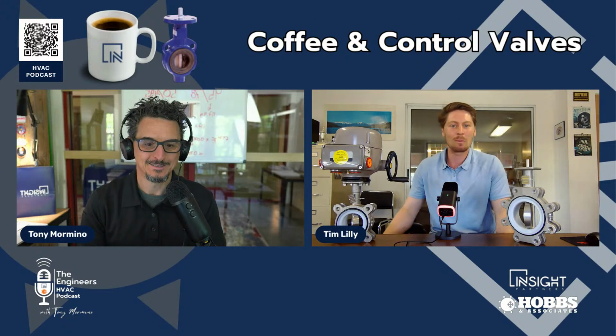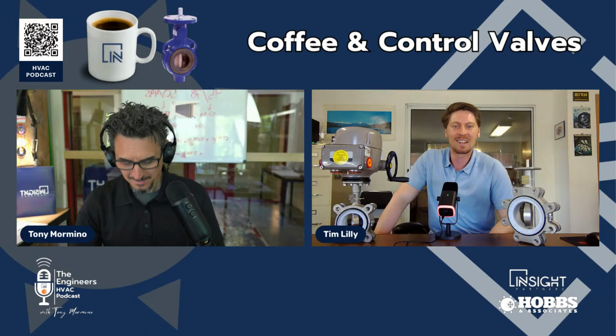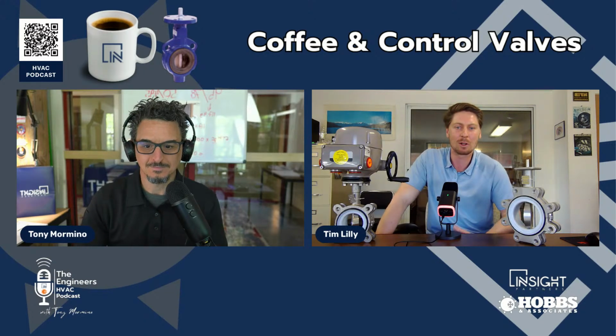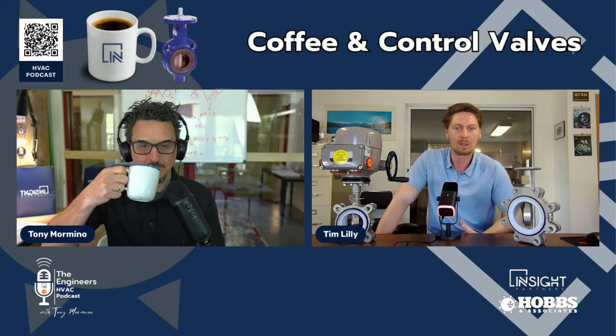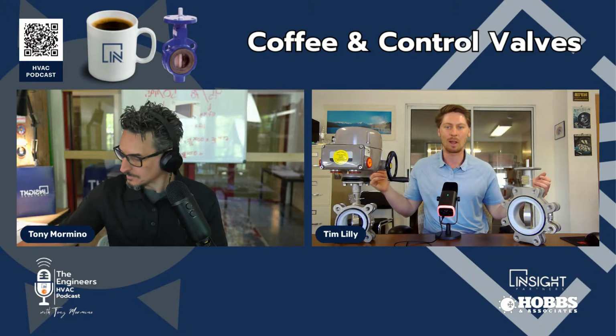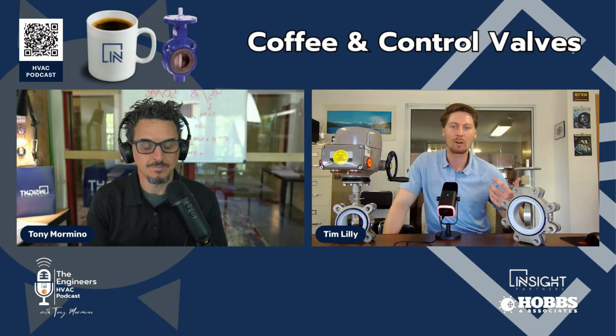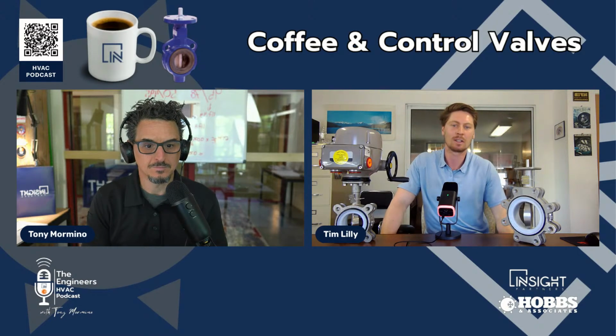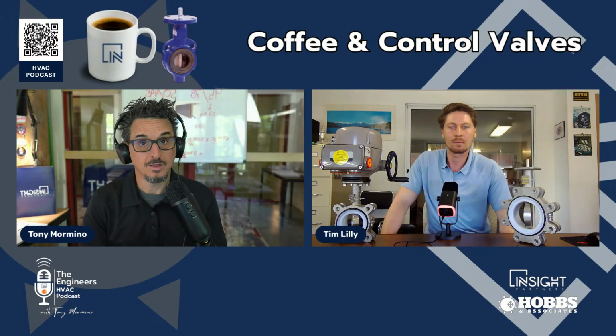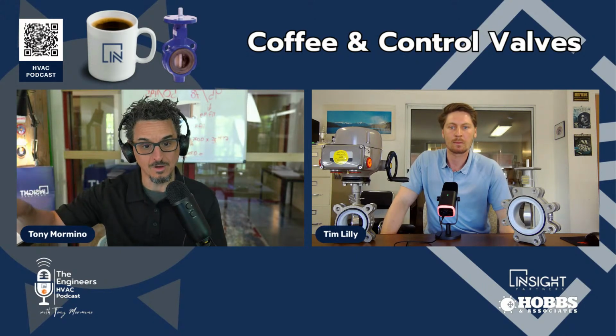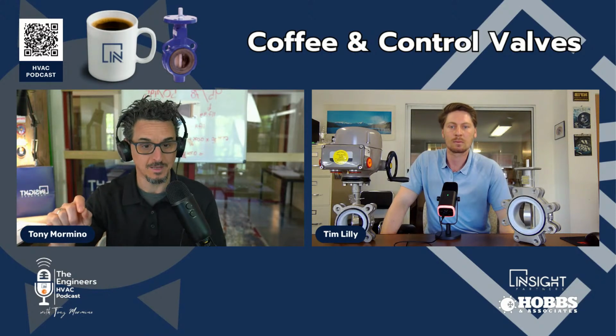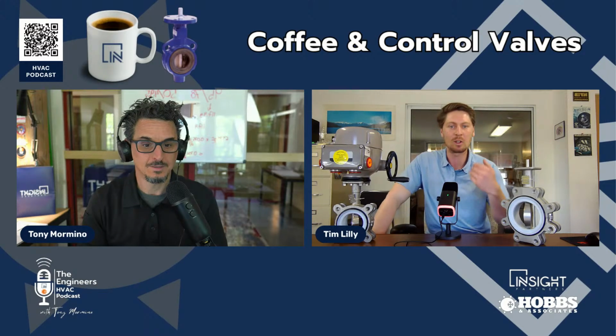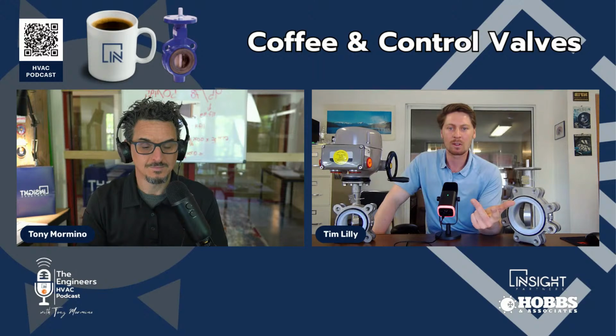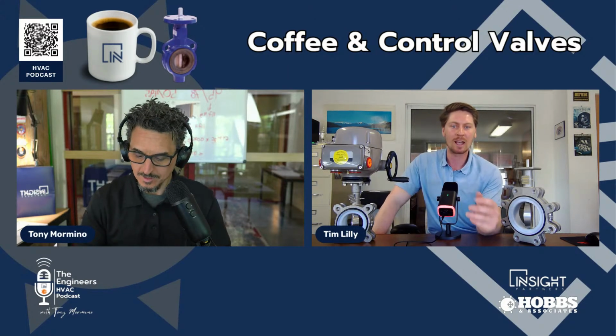Yes. So valve sizing, you do it based on what's called CV. I was hoping you'd bring up CV. And it's a coefficient. What it does is it takes into account your pressure, your flow, your temperature, and your liquid. So it's basically just a way to put everything on the exact same playing field. That way you can size for every single application, and it's a standardized unit. So the valve has a CV assigned to it, correct? Correct. And you pick that CV based on the pressure drop through the coil and the flow. Am I saying that correctly? Yes. So to calculate your CV, you have an inlet pressure, an outlet pressure, your flow, and then temperature. And in most cases, it's going to be water. But if you get into glycol, it's a little bit different because you have the density of the fluid. And then glycol, right?